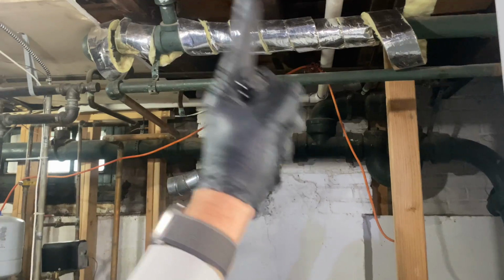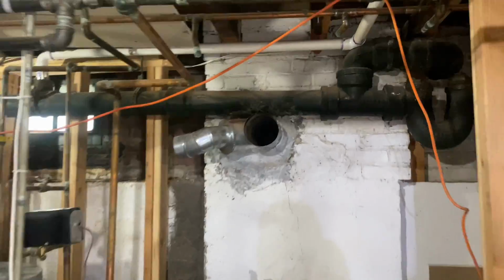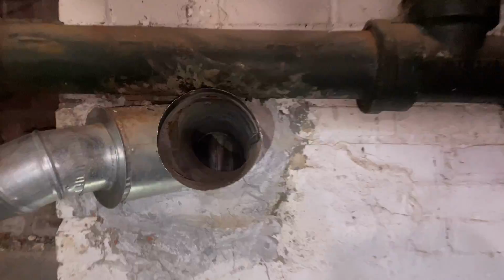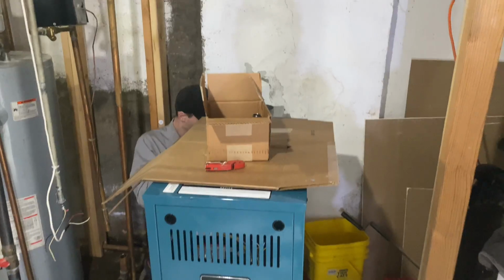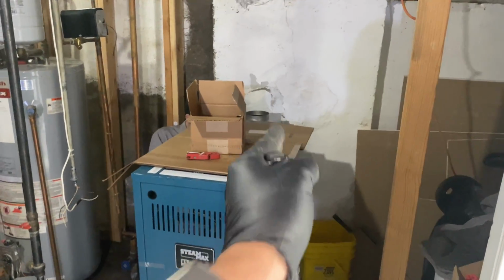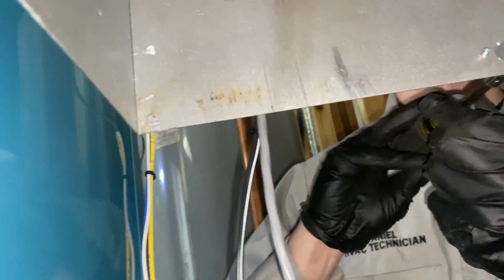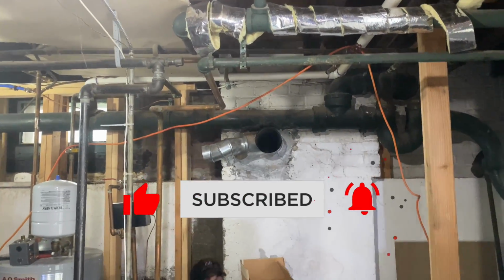Think about a condensing boiler. The very acidic condensate will eat away the terracotta lining of that chimney, and eventually it will collapse upon itself, and then you'll have a blocked vent situation. If you have a blocked vent switch, like you have right here, I'll just pan to the other side, right there. If the chimney were to collapse upon itself, or a bird's nest or something prevents the exhaust gases from going up the chimney, that should go off.